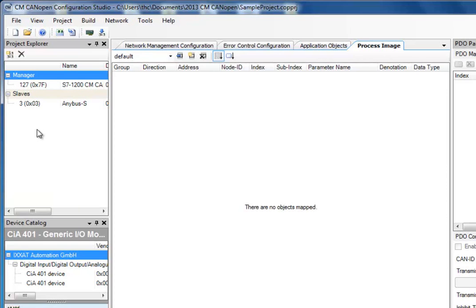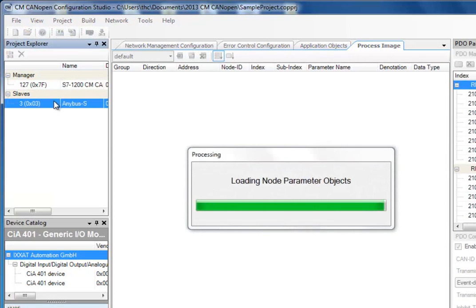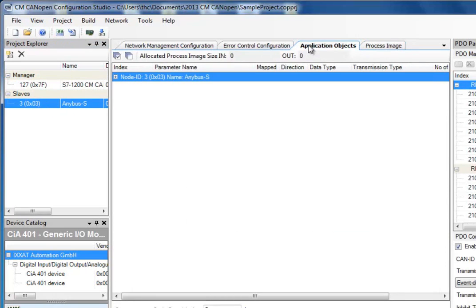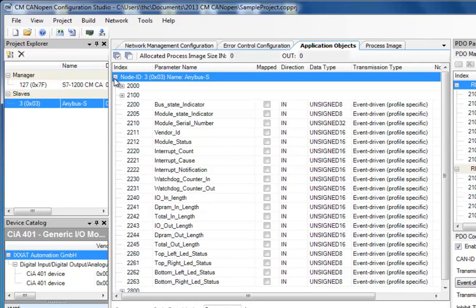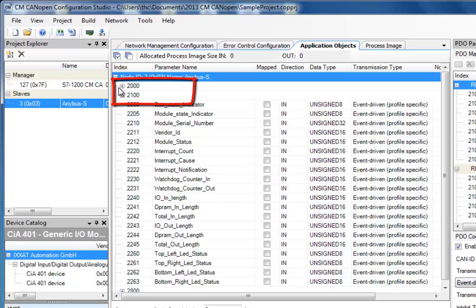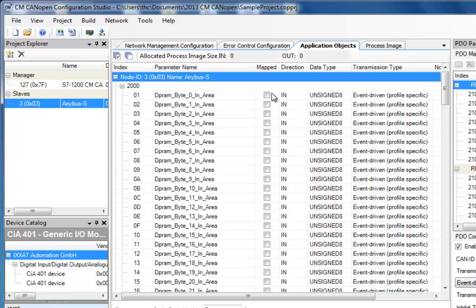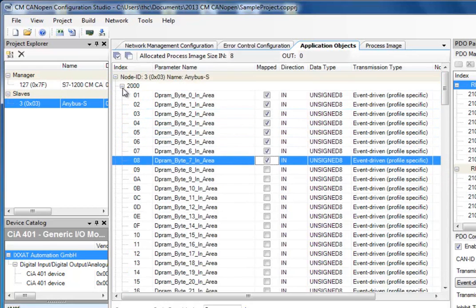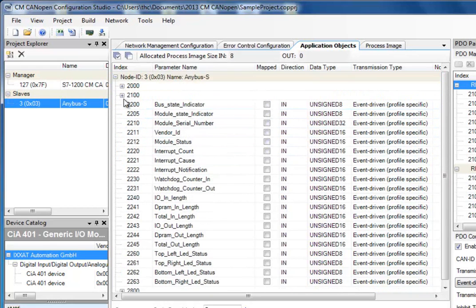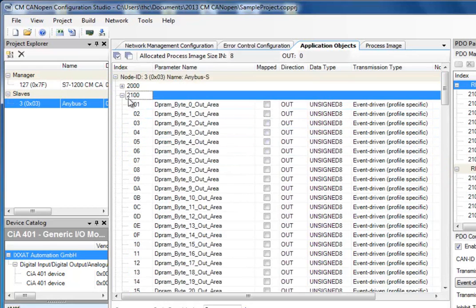I do this by selecting the in and out areas for my slave device. I select my slave and then go to the tab Application Objects. Here I find a list of all the objects that are possible to map as process data. As you may remember, we have specified that we want to send and receive 8 bytes between the manager and the slave. These bytes can be found in the tabs 2000 and 2100. I select the 8 bytes going into the slave and the 8 bytes going out from the slave.